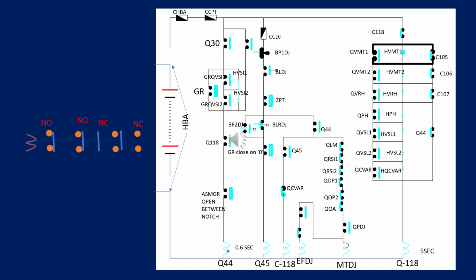After Q118 is energized, your Q44 will be energized. When Q44 is energized, it will close the normally open contact on the EFDJ and MTDJ branch. On the EFDJ MTDJ top, there is the Q44 contact. Then on the MTDJ, so many normally closed contacts are there, so the DC positive will come and energize the MTDJ. From this branch again, C118 is in closed condition, DJ normally closed condition, now DJ is in open condition, so EFDJ will be energized. When EFDJ is energized, your circuit breaker will be closed. This EFDJ relay is for closing the circuit breaker, so DJ is closed.